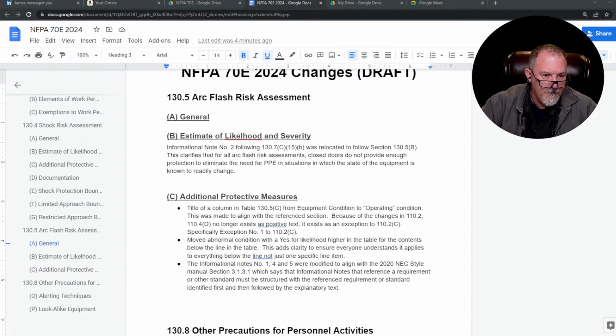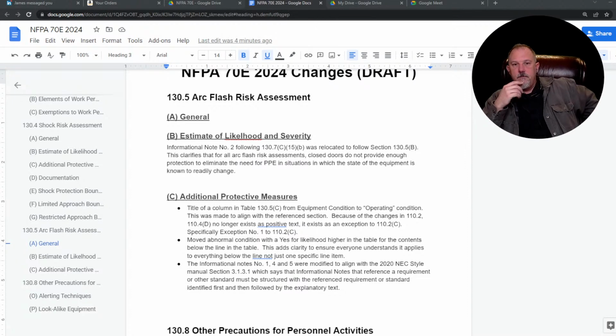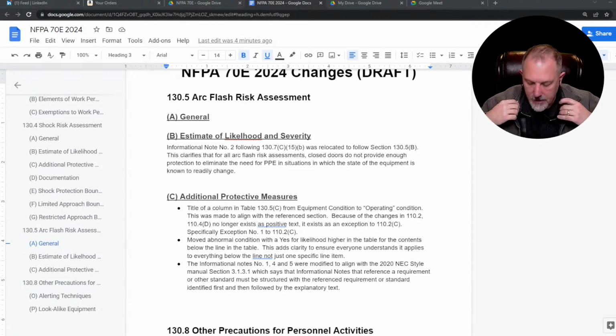Why? What does that mean? It means when you go and pull a breaker handle, you need to estimate the likelihood and the severity when you switch a main breaker, for instance. And if the main breaker covers are in place, you still have to recognize that there is a probability of an arc flash problem when you switch a disconnect. Well, but if it is properly maintained, there's no hazard. And what I do is I go to, how do we know that?